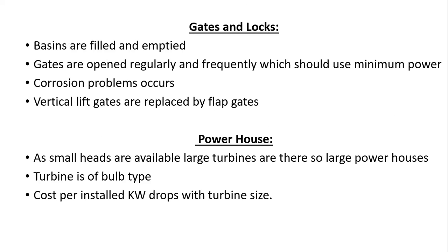Now coming to the gates and locks. These tidal power basins have to be filled and emptied always. Gates are opened regularly and frequently, but heads vary in height and the gates are located on the side where they occur, which is not the case with conventional river projects. So these gates must be opened and closed rapidly, and this operation should use a minimum of power also.